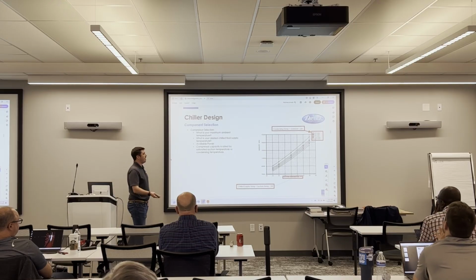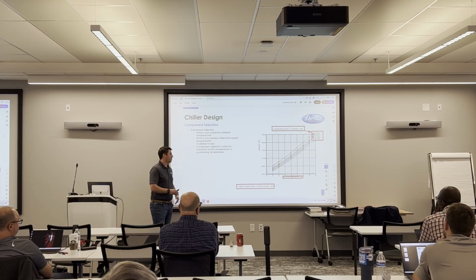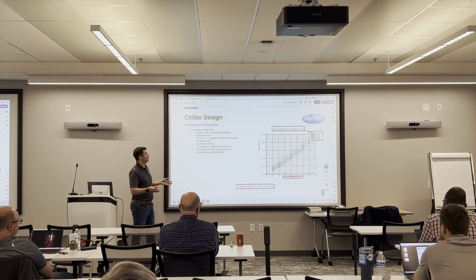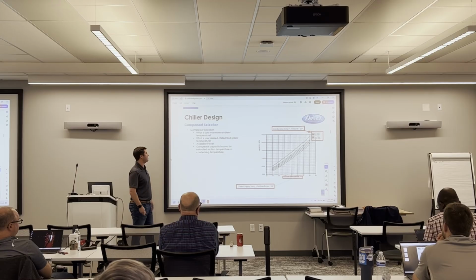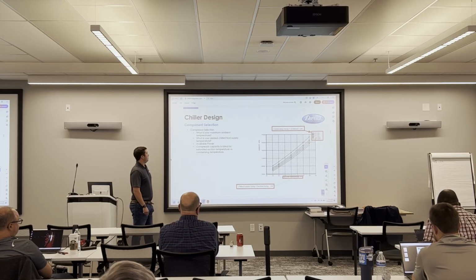So let's say we calculated our heat load from the information that the customer gave us. Now we've got to pick the compressor. It's the first component we have to select, because all the other components follow suit with the compressor in terms of tonnage and capacity. So what do you need to know to size the proper compressor?